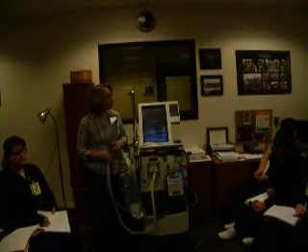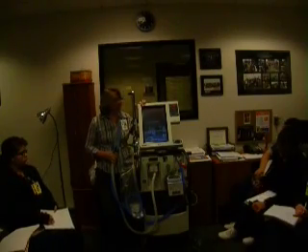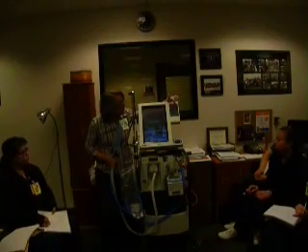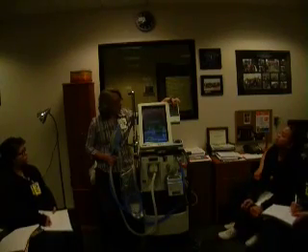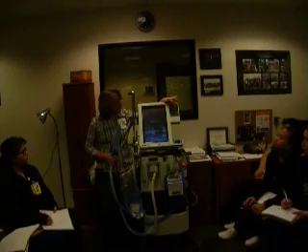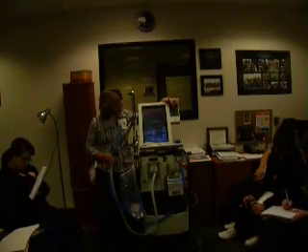I don't think I'm going to be able to simulate the other alarms because we have an O2 alarm, and as long as that's going, you're going to get a high priority. But when we can hook it up in the class back up with oxygen, I'll show you the difference. See over here to the left, there's a top one, a middle one, and a bottom one. Depending on which alarm, it will light up differently. This is more like an orange, and this is more like a yellow. So high priority, medium priority, low.